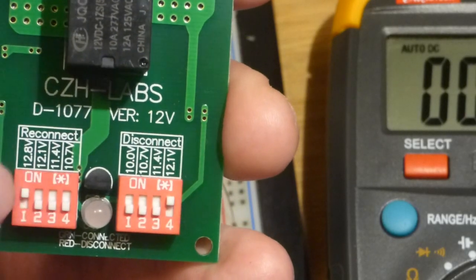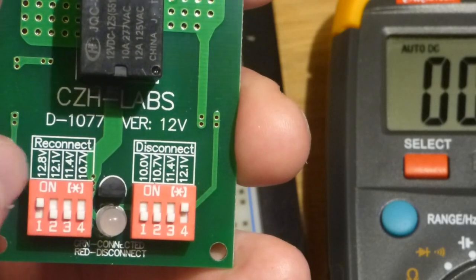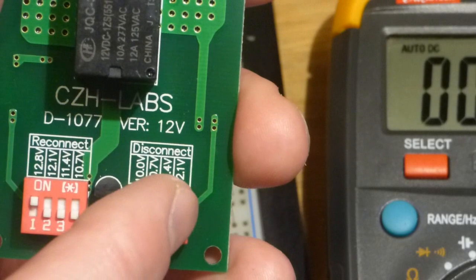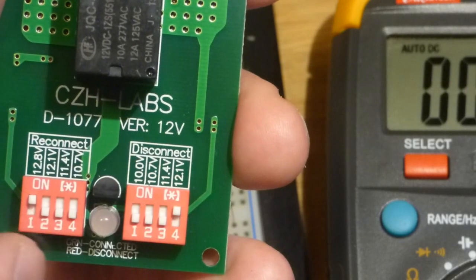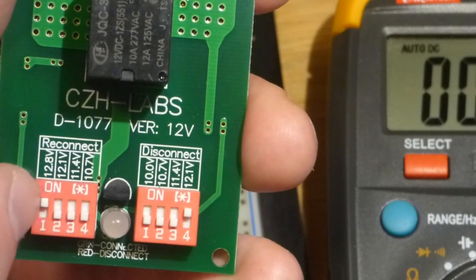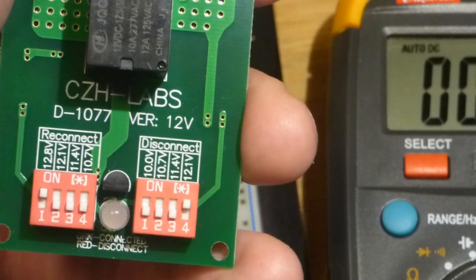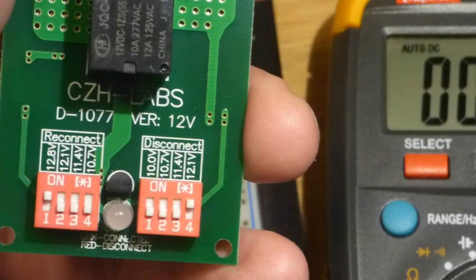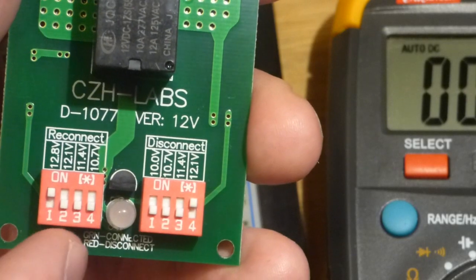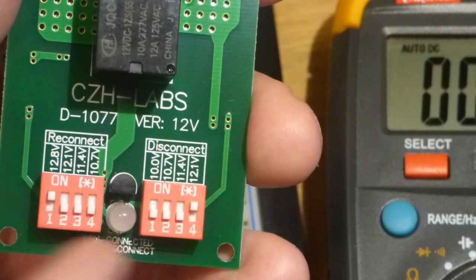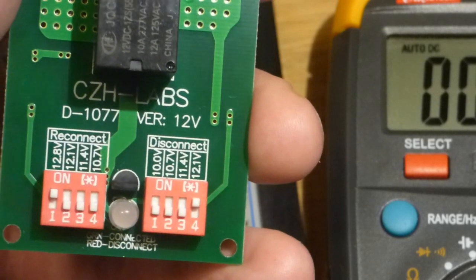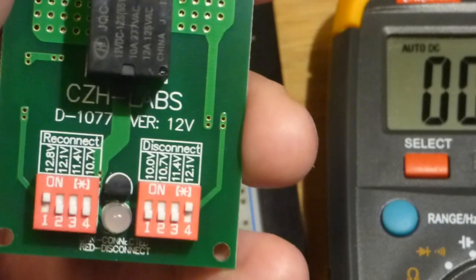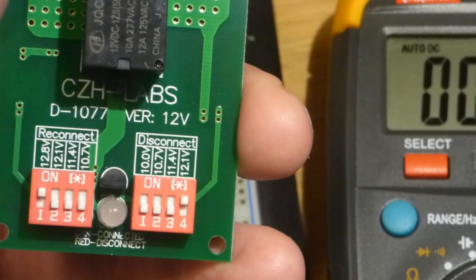And then the reconnect, the reconnect number is higher. So I set this one to 12.1 volts and then this one to 12.8 volts. So we have a range, you discharge it, it turns off, then it lets you recharge it past where it turned off before it turns back on again. That way it's not flickering on and off rapidly.